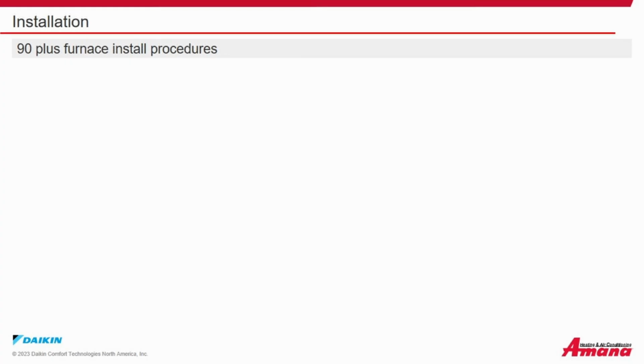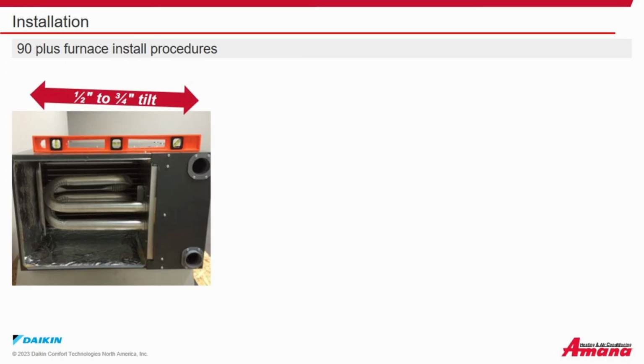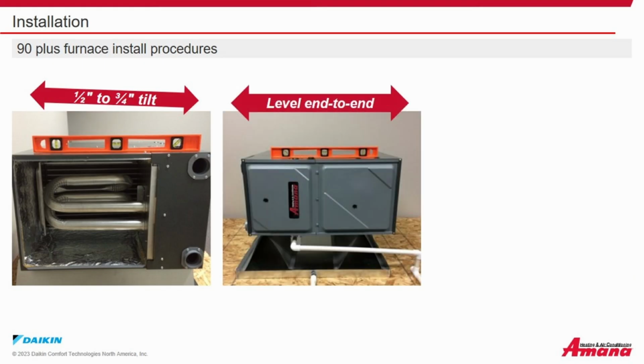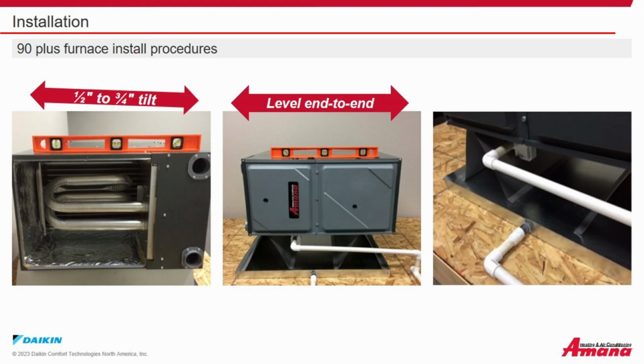The procedure for installing a 90+ gas furnace. There should be a 1/2 to 3/4 inch tilt toward the front of the furnace and level from end to end. When in an attic, it is always best practice to install an auxiliary drain pan under the indoor unit.